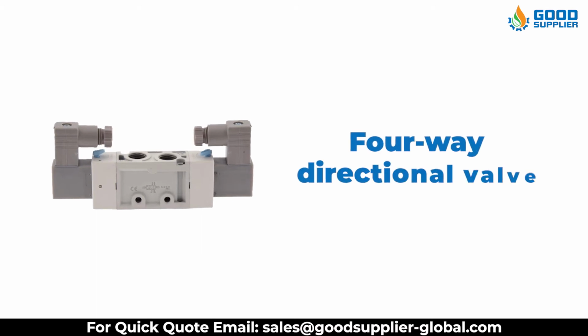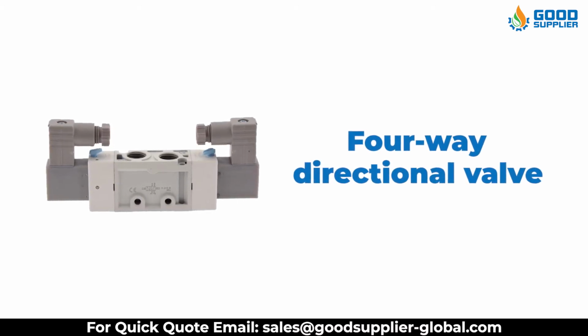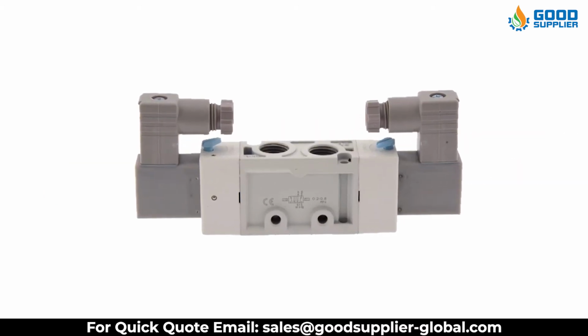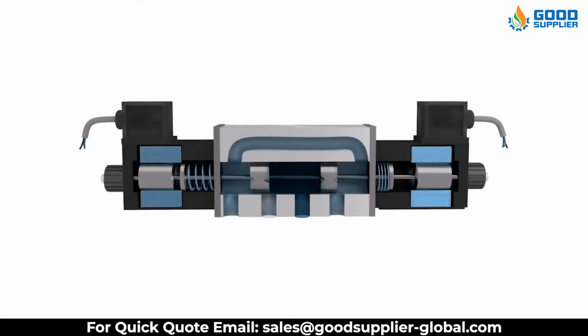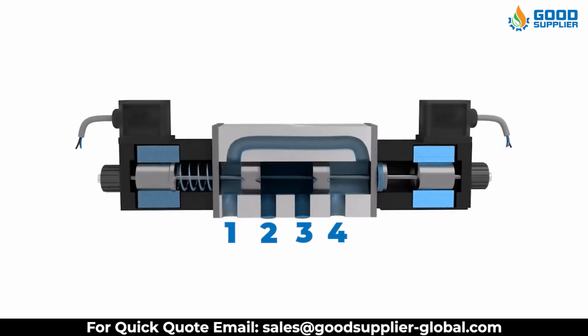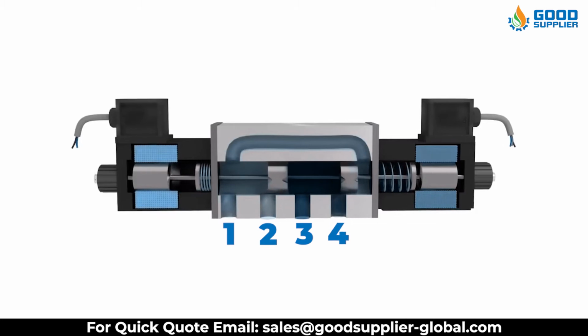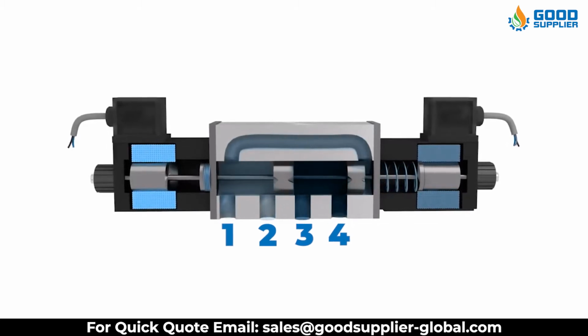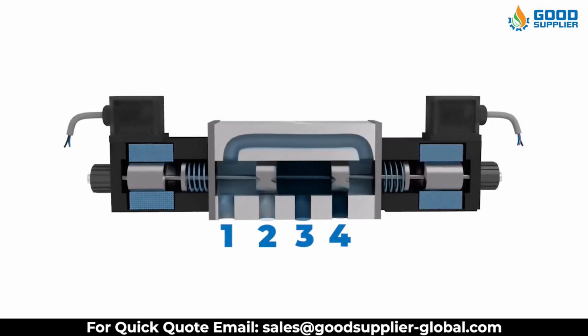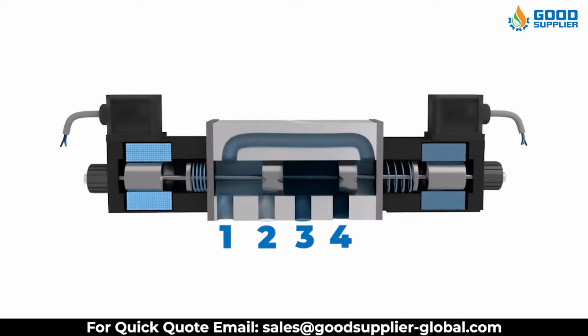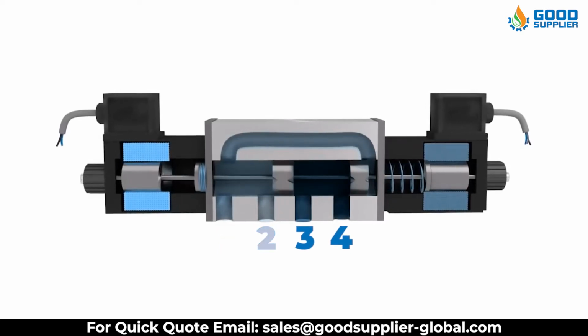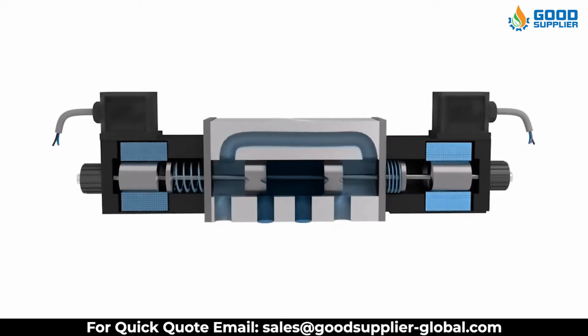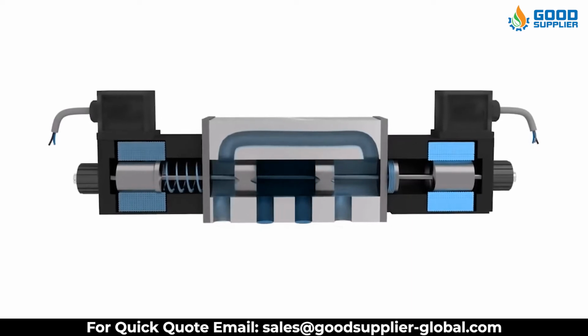A 4-way directional valve has 4 distinct ports, 2 of which connect to actuators, one that connects to a pressurized airflow, and one that serves as an exhaust pathway. They are among the most common types of valves found in pneumatic systems because the 4 distinct paths allow the valve to effectively reverse the motion of a motor or basic cylinder.